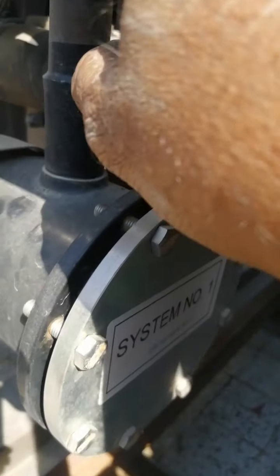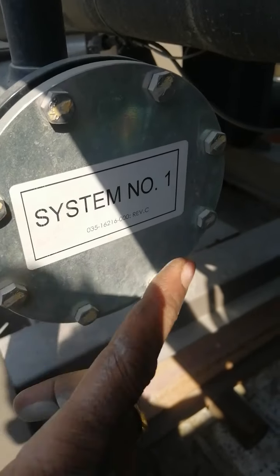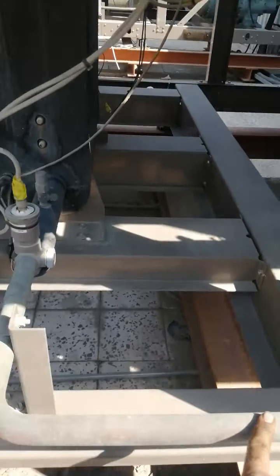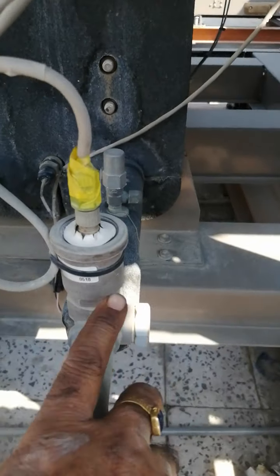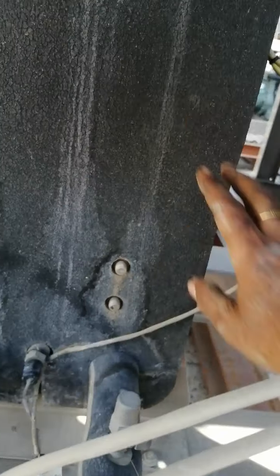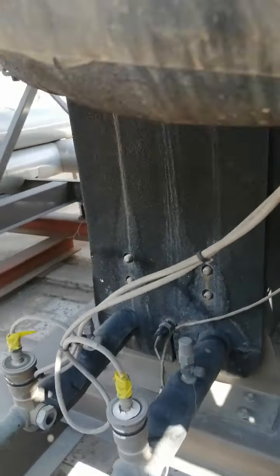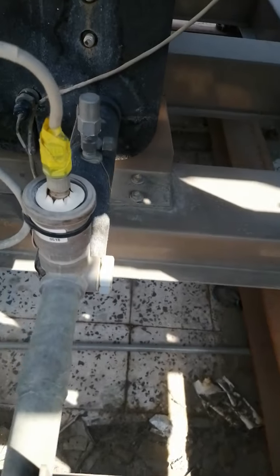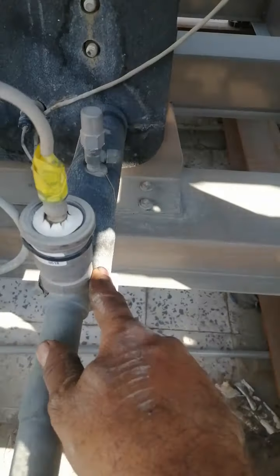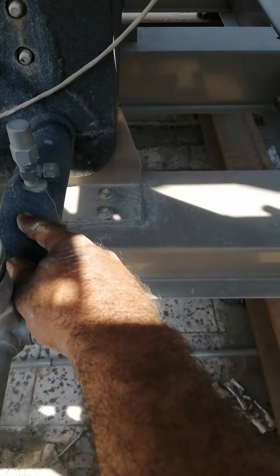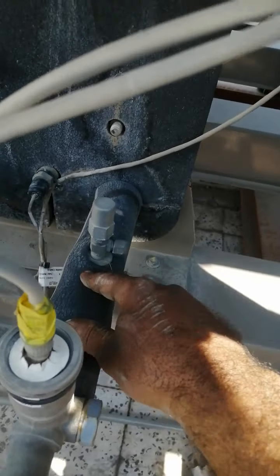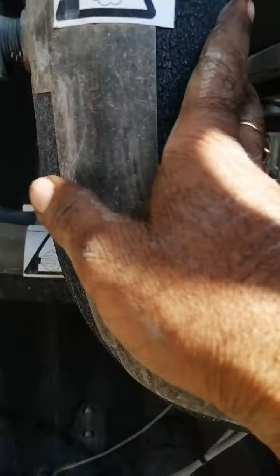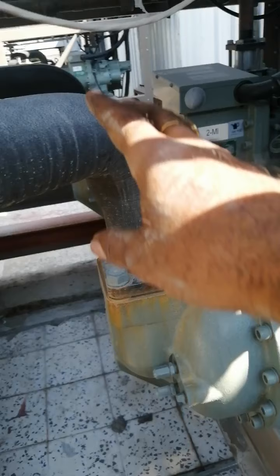You see my finger. This is coming to the filter. Okay, system number 1 filter. After the system number 1 filter, it is going to the electronic expansion valve. After the electronic expansion valve, it is going to the plate heat exchanger. As you see, this is a plate heat exchanger, not tube type. It is a plate heat exchanger. So the refrigerant is going from this liquid, and after the expansion valve it is converted to low pressure liquid, and after that it is low pressure vapor. This is going to suction. This is the suction port of the compressor.